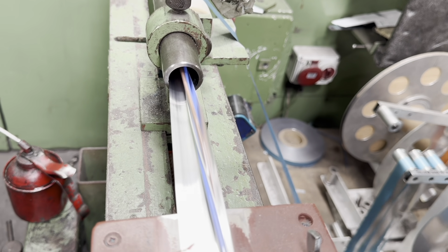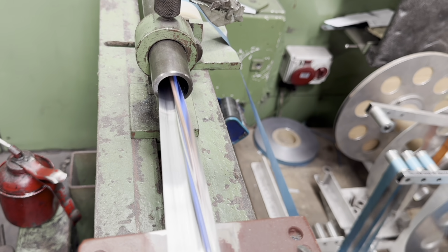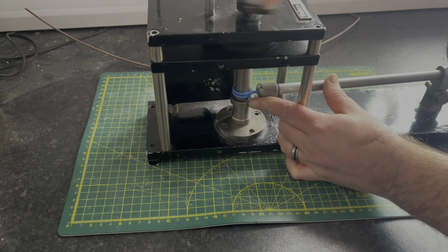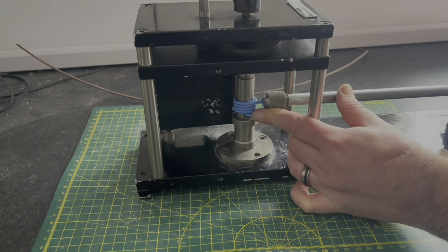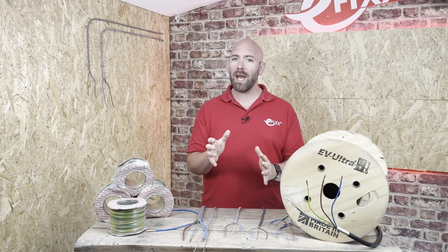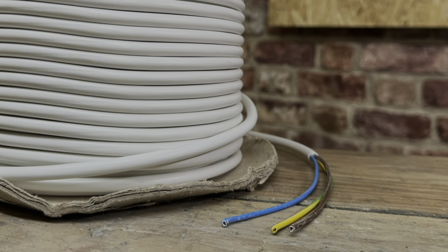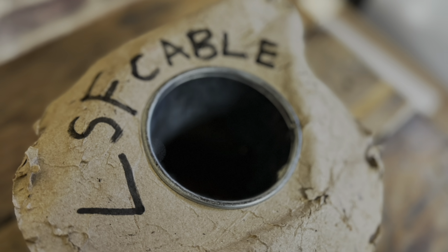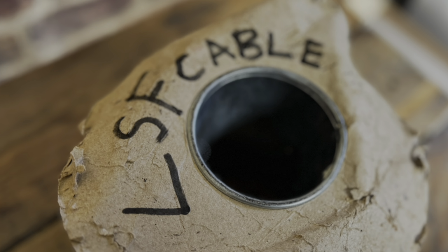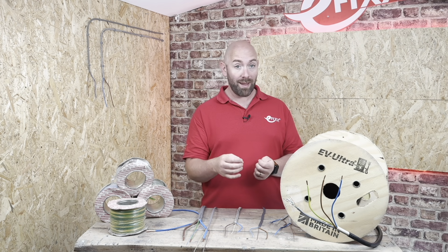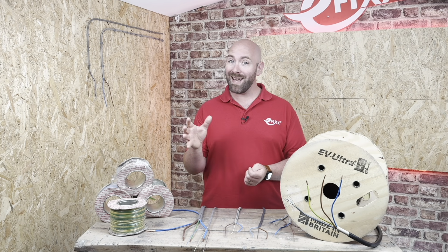This cable is manufactured by Doncaster Cables and as such made to meet the British and harmonised standards for low smoke, zero halogen cables. And the composition of this cable meets those standards and will not emit dangerous smoke and fumes if it's in a fire. This one, however, is made with much cheaper materials and a lower copper density, something that can only be recognised by testing in a laboratory. And with cheaper imported cable coming into the UK market, we are running the risk of installing a cable we think conforms to standards, but actually it doesn't.